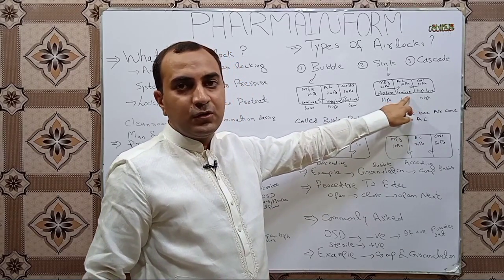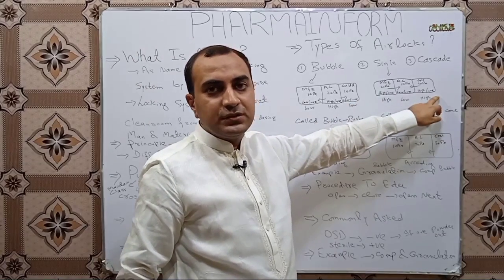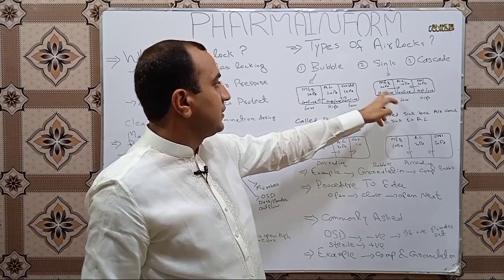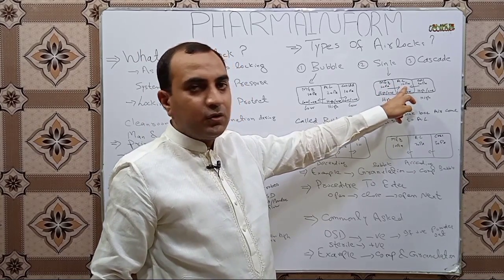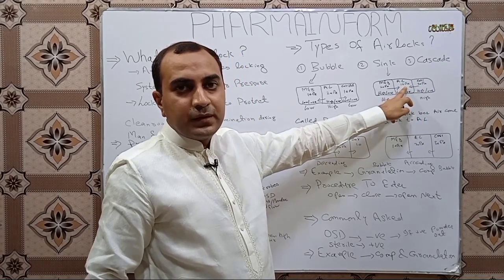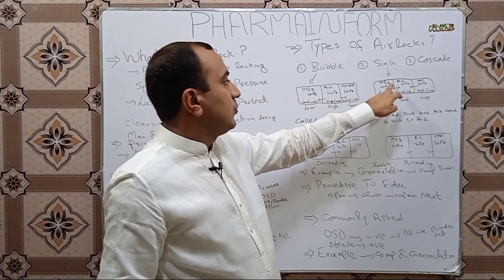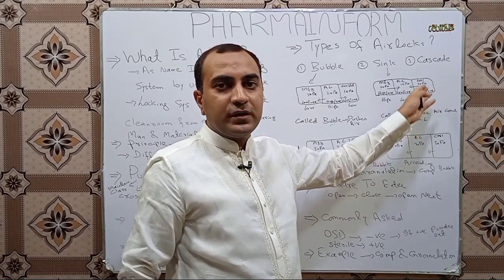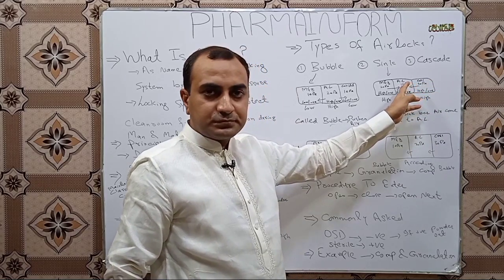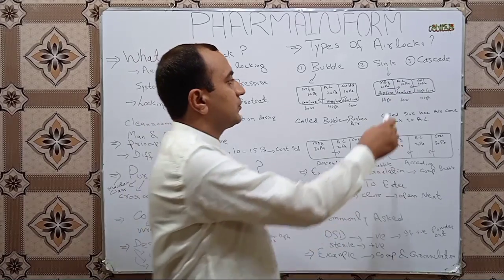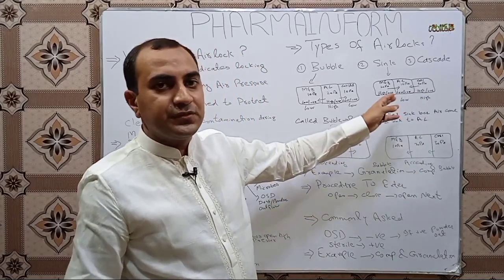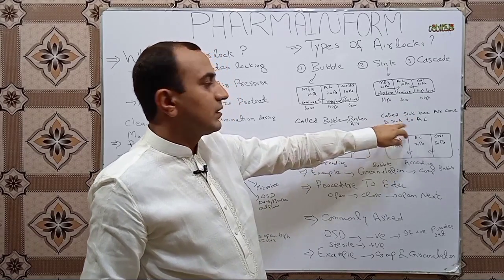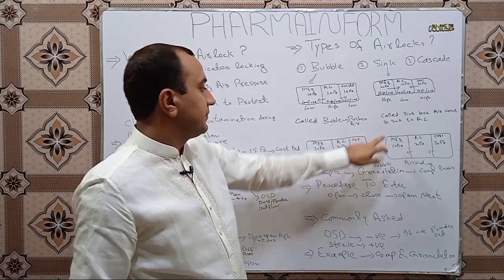In a sink airlock, we have low pressure in the airlock and higher pressure in both the manufacturing area and the corridor. Air from the manufacturing area comes into the airlock, and air from the corridor also comes into the airlock. So when we open either door, air always flows into the airlock from both sides, preventing cross contamination between the manufacturing area and the corridor. This system is known as the sink airlock.